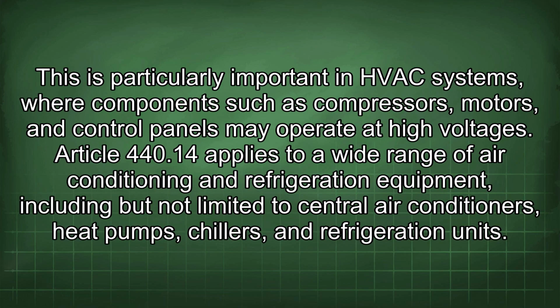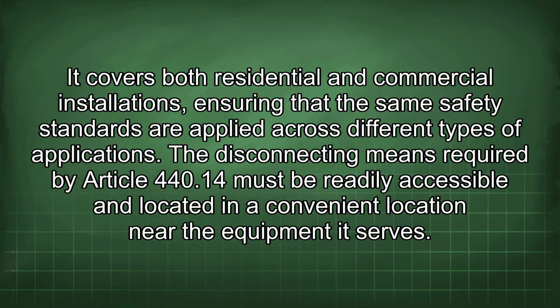This is particularly important in HVAC systems, where components such as compressors, motors, and control panels may operate at high voltages. Article 440.14 applies to a wide range of air conditioning and refrigeration equipment, including but not limited to central air conditioners, heat pumps, chillers, and refrigeration units. It covers both residential and commercial installations, ensuring that the same safety standards are applied across different types of applications.